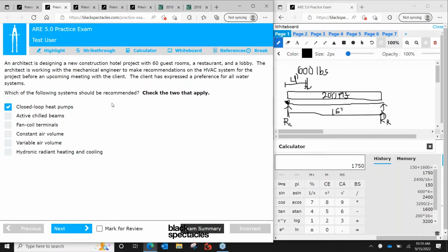All right, next we have active chilled beams. So active chilled beams include both air and water system elements and can perform heating or cooling. Outside air is treated at a central fan room, then ducted to individual floors and rooms. Chilled or heated water from the boiler room or chilled water plant is then piped to each individual floor or room. At the room, the supply air is mixed with existing room air, then blown over the pipes to heat or cool the air. This system can be individually controlled, influencing the flow of water in the pipes. Since this is not an all-water system, we can eliminate this option.